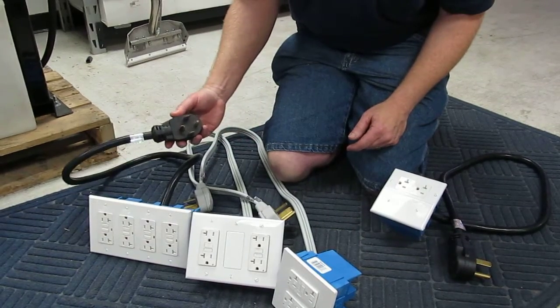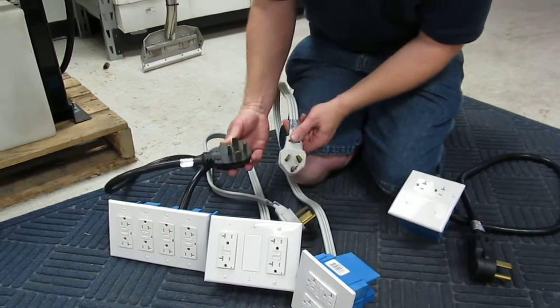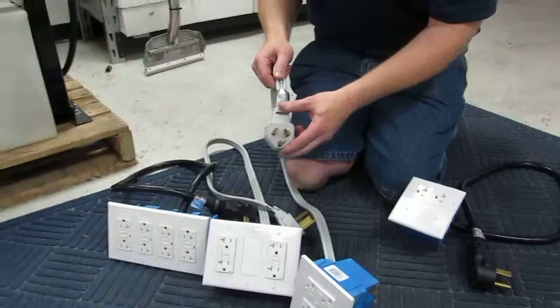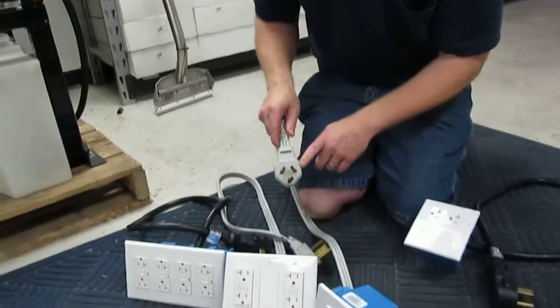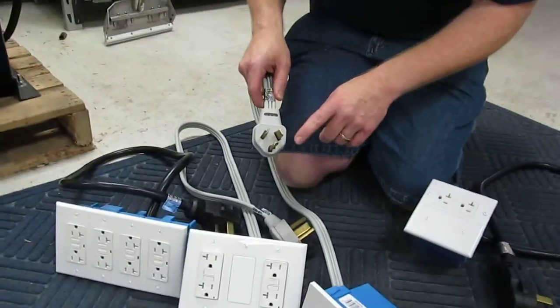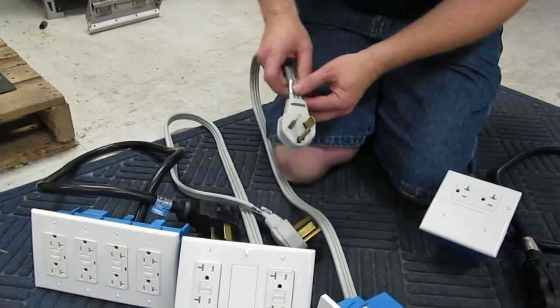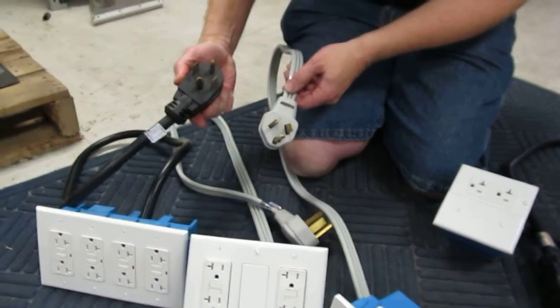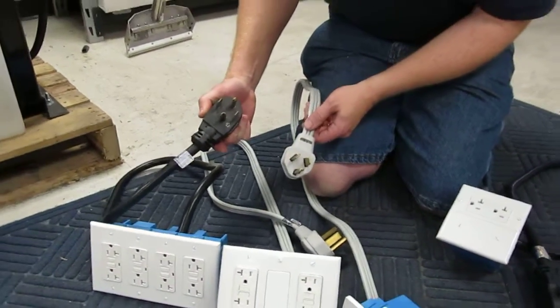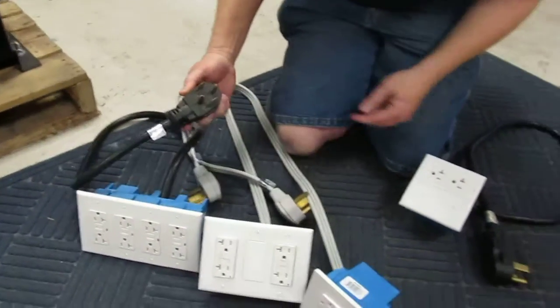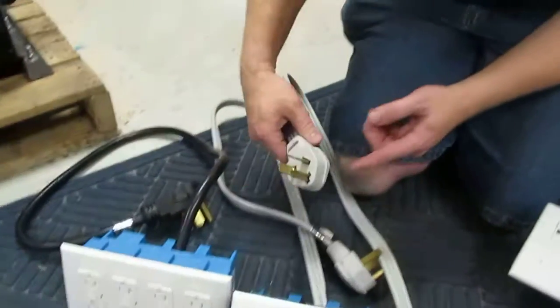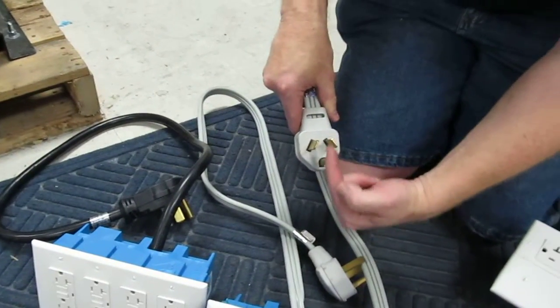So if you're straight on the common here, then that means that it's going to be rated for 50 amps. So for example, on this one, this is primarily used in older homes typically built before 1987. This is a 30 amp 3-prong, and this is a 30 amp 4-wire or 4-prong connector. There'll be a 4-prong 50 amp, which will have a straight leg, and then there's also a 3-wire 50 amp, which will be straight right here.